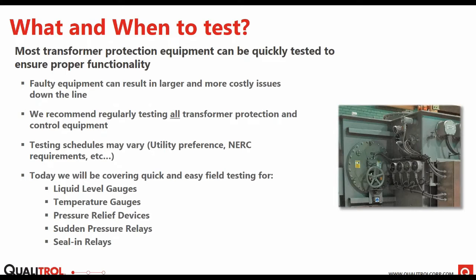And the reason you want to do this is because faulty equipment can result in much larger and more costly issues down the line. For example, an undetected sudden pressurizing of your transformer can result in a catastrophic failure. Inoperable switches on, say, your thermometer for cooling, and you don't have your cooling stages coming on, that can lead to much bigger potential issues. So here at Qualitrol, we recommend to test all protection equipment that is either tied back to an alarm or control circuit, and the trip. You can include trip in there too.